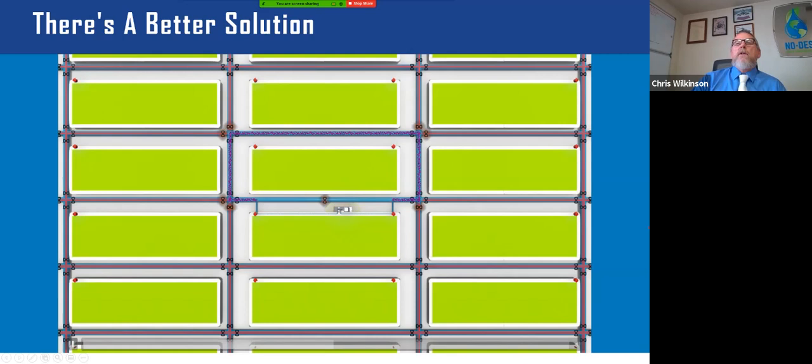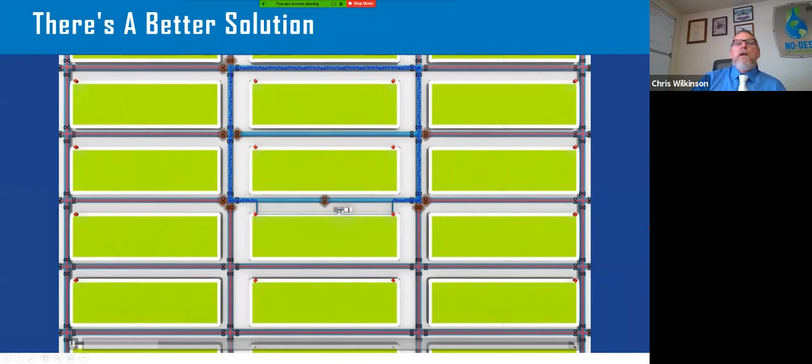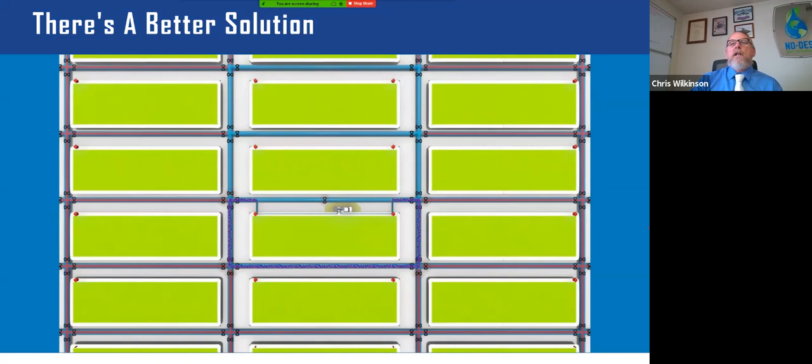We've just created a hydraulic loop to where our flushing flow goes exactly where we want it to go, around the block. Once this gets done, 15, 20 minutes, then we can do the same. We stay here and we go around the block this way. And then we just do that over and over again. As you can see, it goes down to the south of our truck. And then we get that clean. It goes down. You can see the lighter blue representing that those mains are clean.